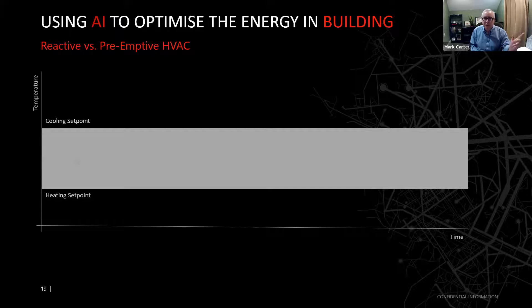So normally under a reactive system, it does not do anything inside the deadband. It actually waits before it hits either the cooling set point or the heating set point before it engages the building HVAC system. But as long as it's within that deadband, it's happy. It's almost like driving a car blindfolded if you have the rumble strips. As long as you're driving along and you're not hitting a rumble strip, you're fine. But as soon as you hit one, you'll veer back into the lane. And if you hit the other side, you'll veer back. And that's essentially what an HVAC system does that's reactive.